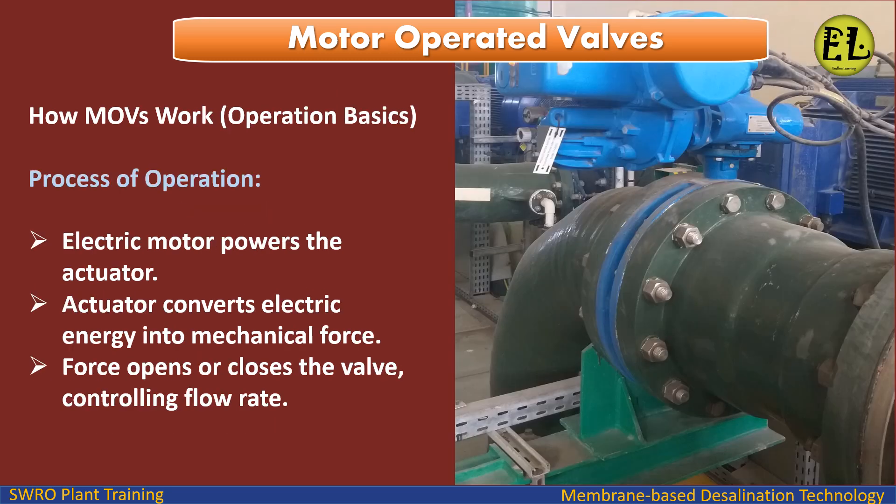Additional components include Limit Switches and Positioners, which control the valve's open/close positions. In operation, the electric motor powers the actuator, which converts electric energy into mechanical force. That force then opens or closes the valve, controlling the flow rate.